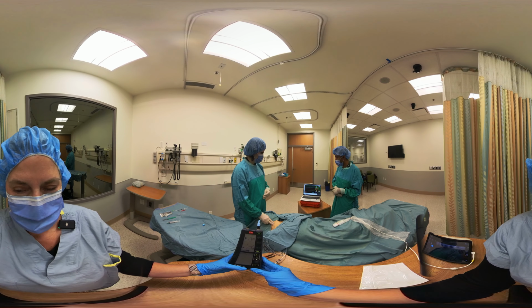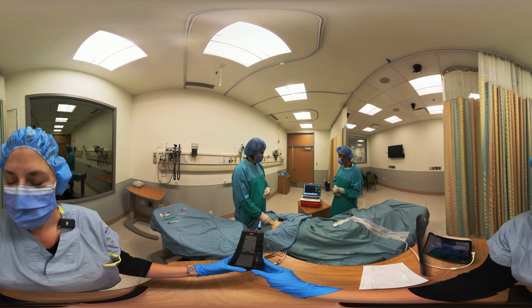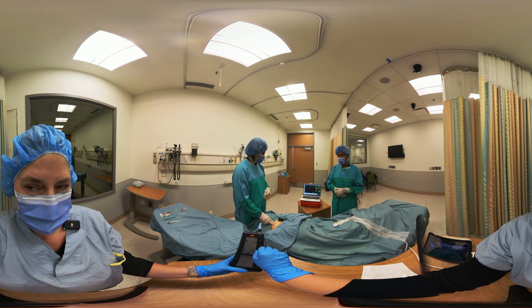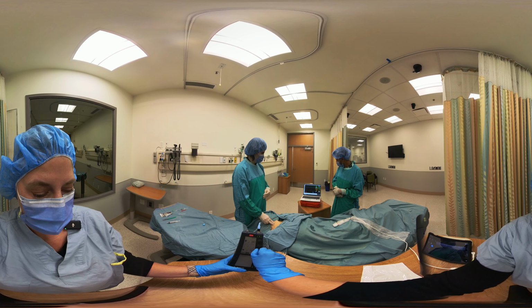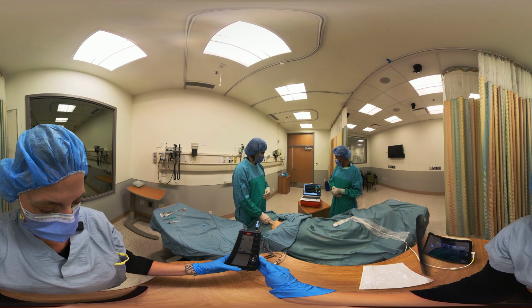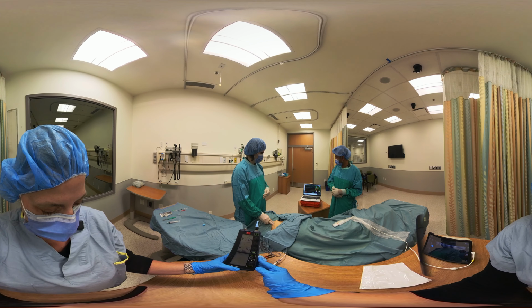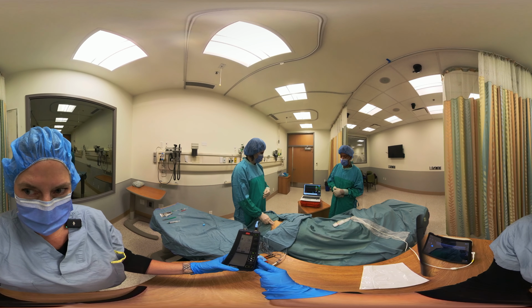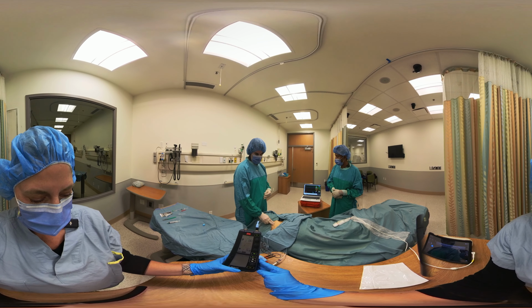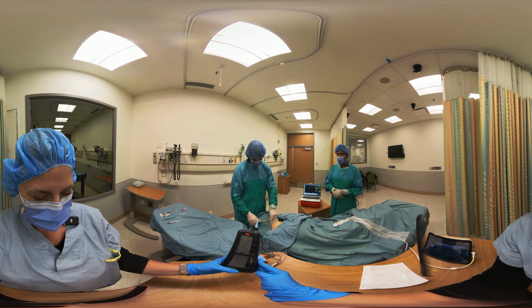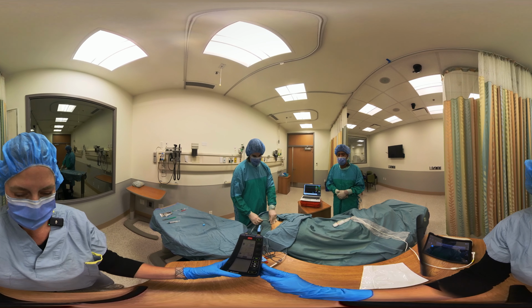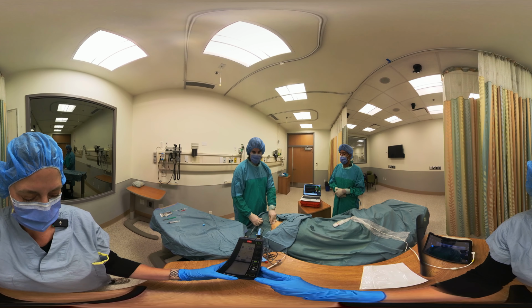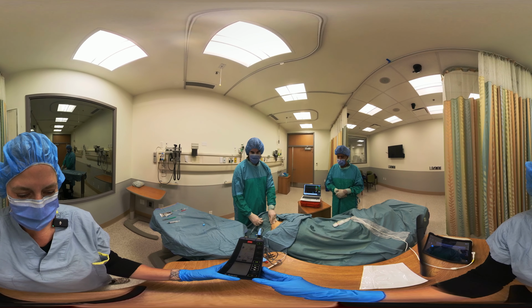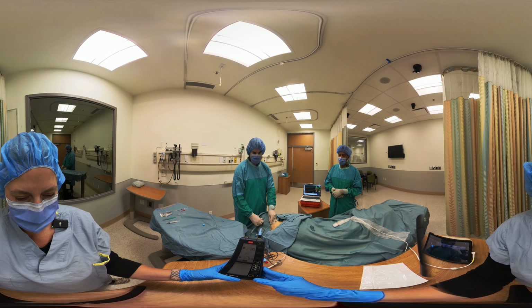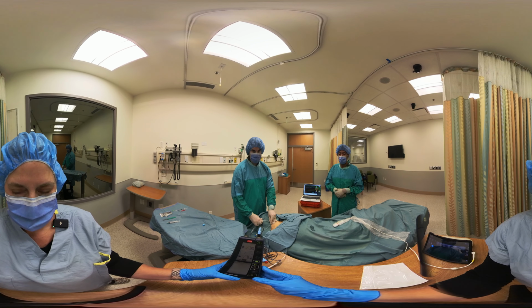For external pacemakers, because we're not worried about battery life, you can even go to 5. So in this case, let's leave the pacemaker at 5 milliamps. And so once you're at 5 milliamps, you can see that the patient is appropriately pacing. It is important to document the depth at which the catheter is, to document what the threshold is, and a pacing threshold test is typically done daily to see if there's a big change in the pacing threshold, because if there is a big change in the pacing threshold, it suggests that the catheter may have potentially moved.